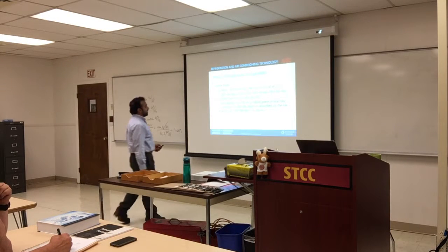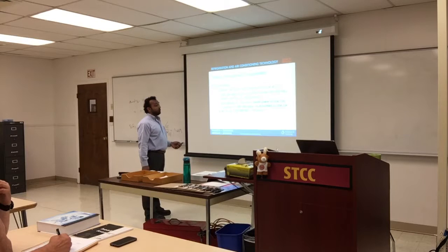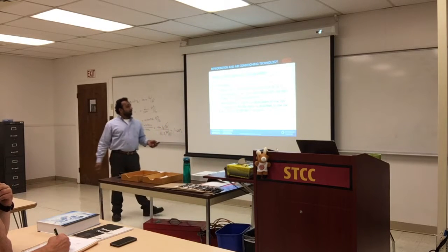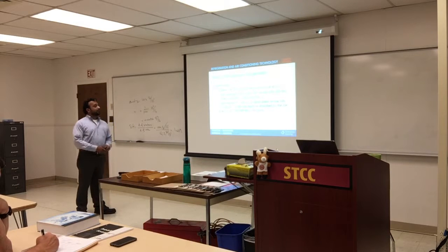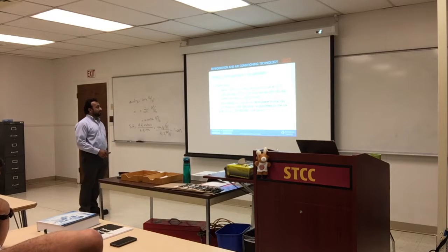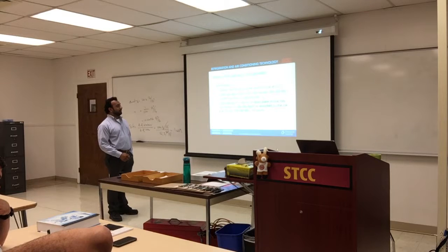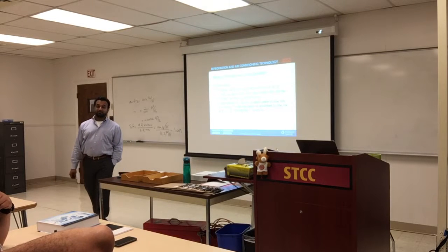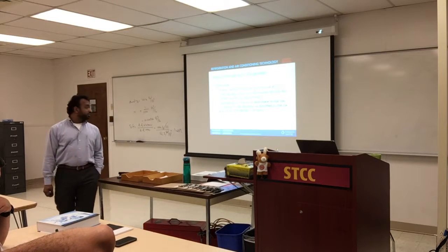So 2,000 pounds of ice, which is 1 ton, will require 288,000 BTU to melt. If we multiply that, we get the conversion. If melting 1 ton of ice takes place in 1 day, 24 hours, we get 12,000 BTU per hour. So 12,000 BTU is the ton of refrigeration.